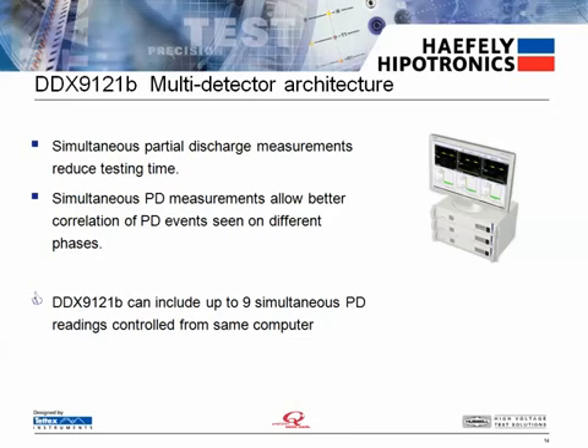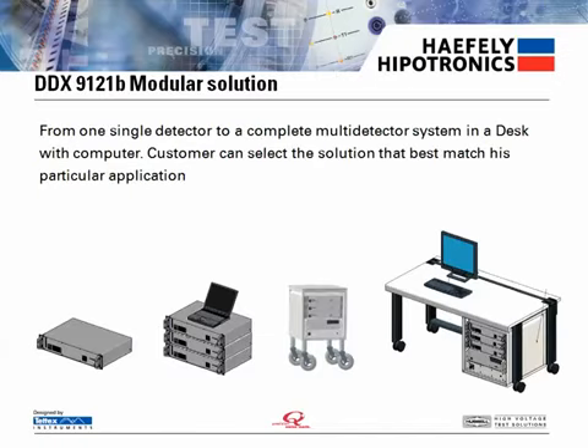In addition to the 4 non-simultaneous inputs of each detector, we can offer multiple detectors for simultaneous measurements to reduce the total testing time. We can offer up to 10 DDX9121B detectors for 9 simultaneous PD readings controlled from just a single computer. From a single detector to a 9 simultaneous channel system, we can offer different needs to meet the custom application, including a cart or a desk.